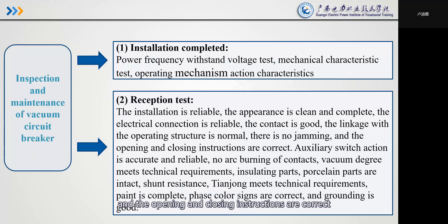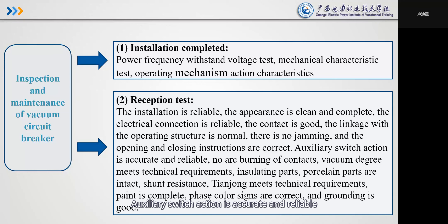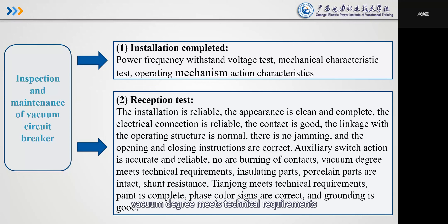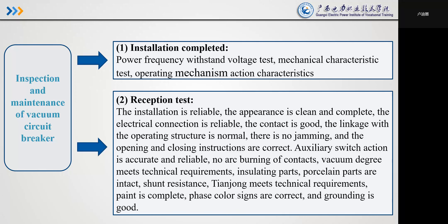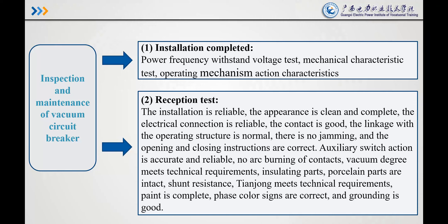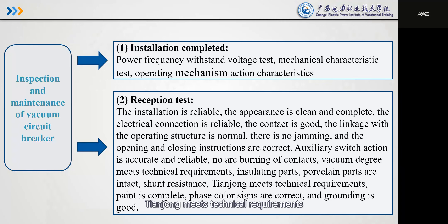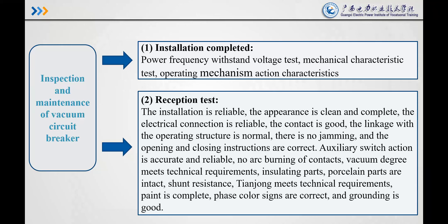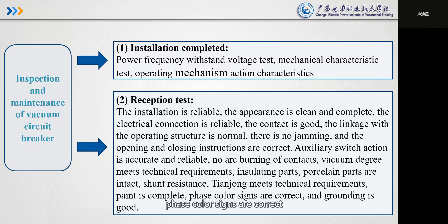Continued installation checks: (7) There is no jamming; (8) The opening and closing indicators are correct; (9) Auxiliary switch action is accurate and reliable; (10) No arc burning of contacts; vacuum degree meets technical requirements; (11) Insulated parts are intact; (12) Shunt resistance meets requirements; (13) Paint is complete, phase color signs are correct; (14) The grounding is good.